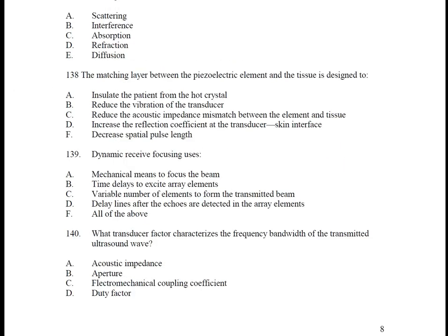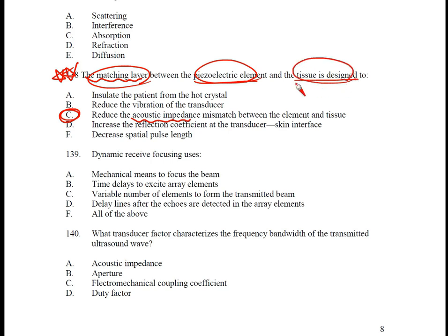Let's look at question 138 right below. This question is related to the structure of the transducer. You could say it's important. This question asks you to choose the option related to the matching layer or coupling layer between the piezoelectric element and the skin. The correct answer would be option C. The characteristic of the coupling layer is that it acts as a bridge by reducing the difference in acoustic impedance between the piezoelectric element and the tissue. In addition, since all matters related to the structure of the probe are important, I want to emphasize that it is essential to solve related questions.